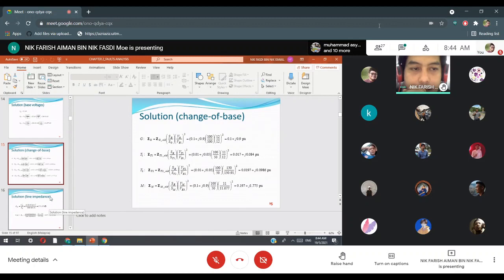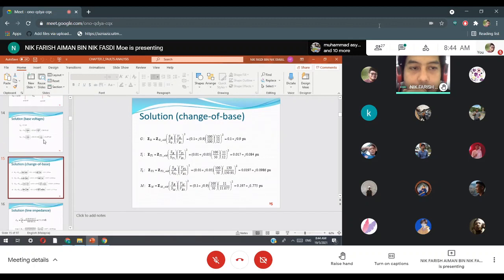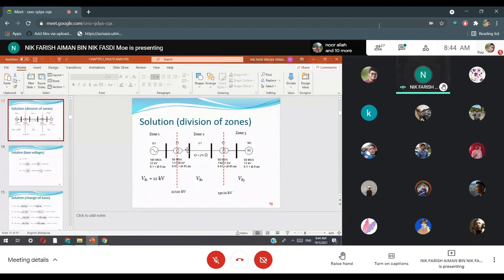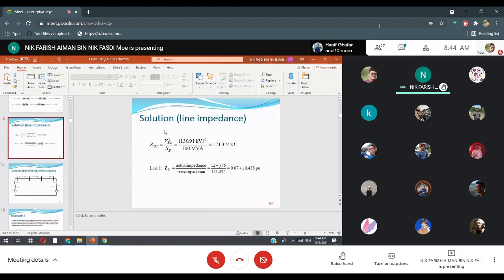The last one you need to determine is the line impedance in per unit, converted from ohms. As usual, you need to convert it to the per unit Z base system. For this case, you first determine Z base 2, because the line is between base 2. This is the value of Z base 2: 130.91 kV squared divided by the 100 MVA base, giving Z base 2 of 171.374.